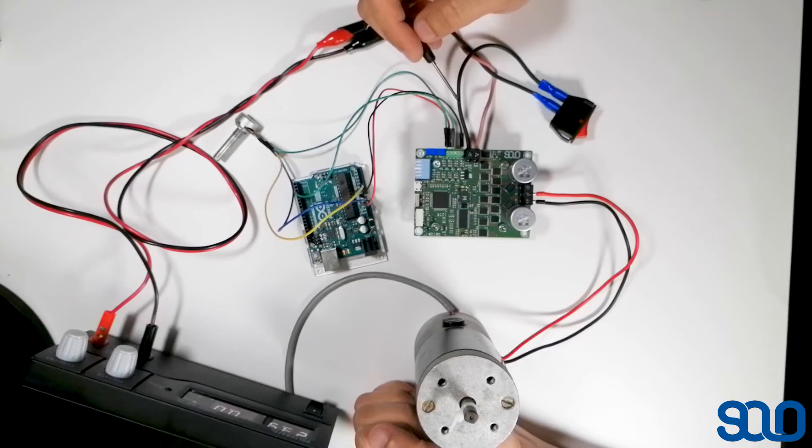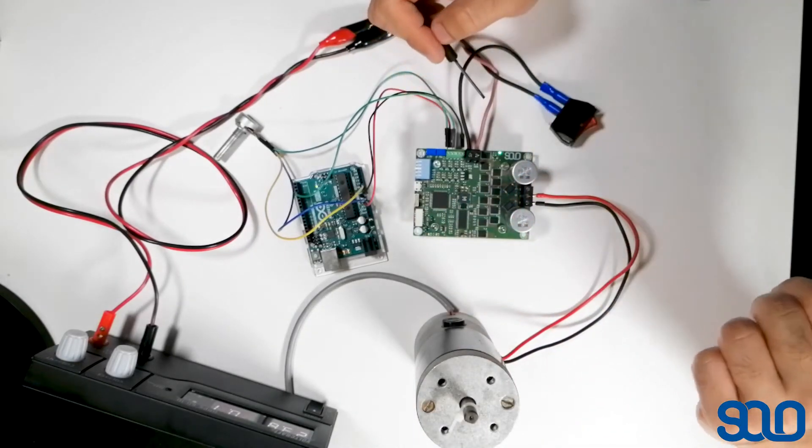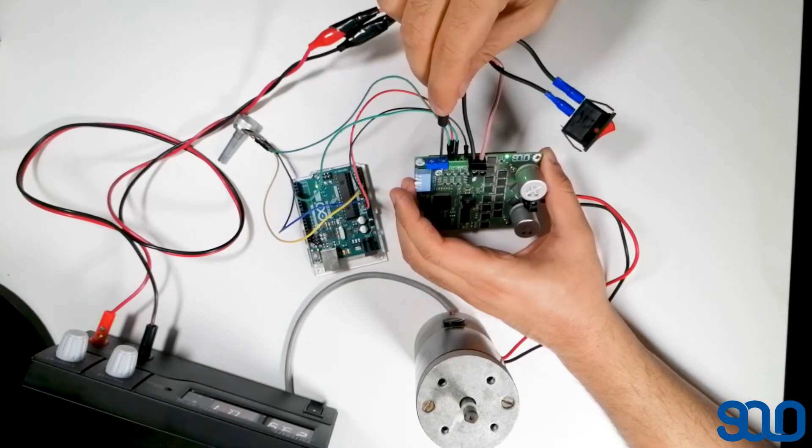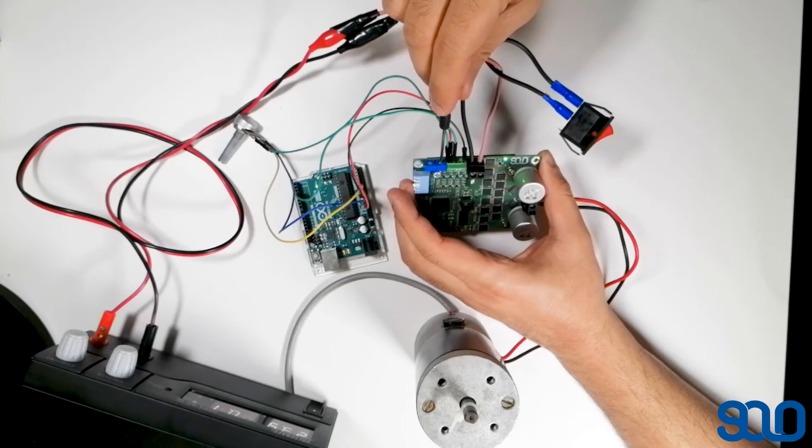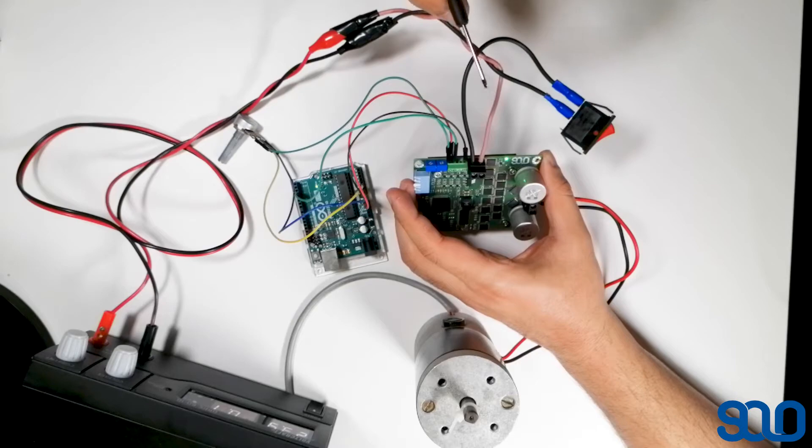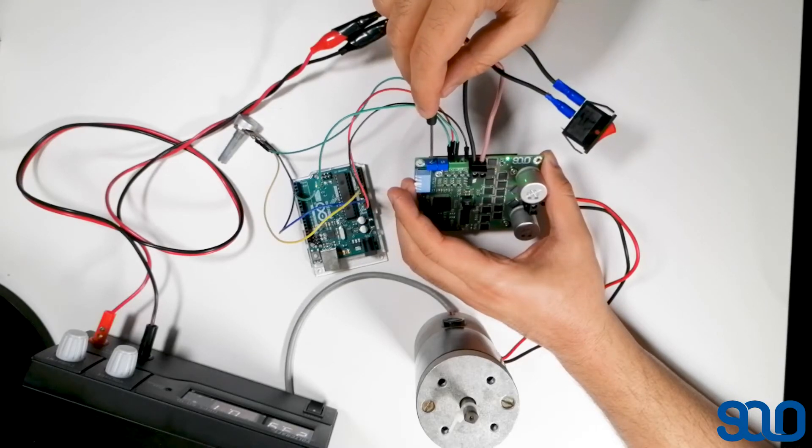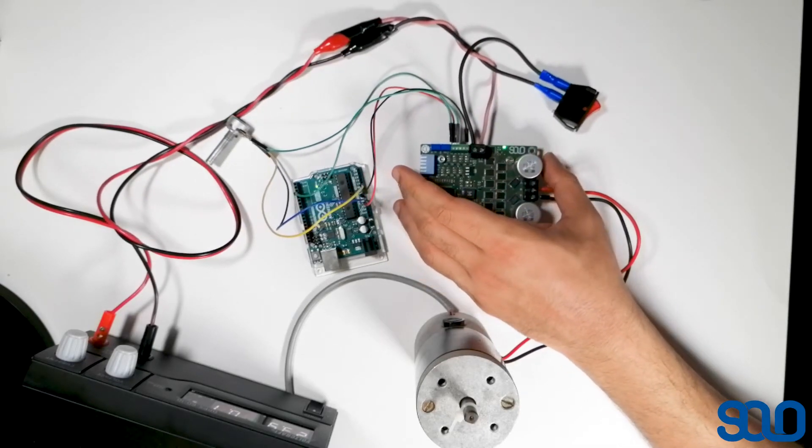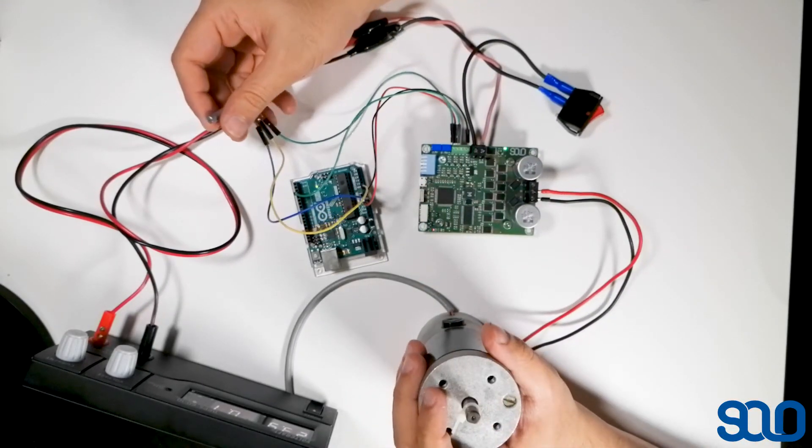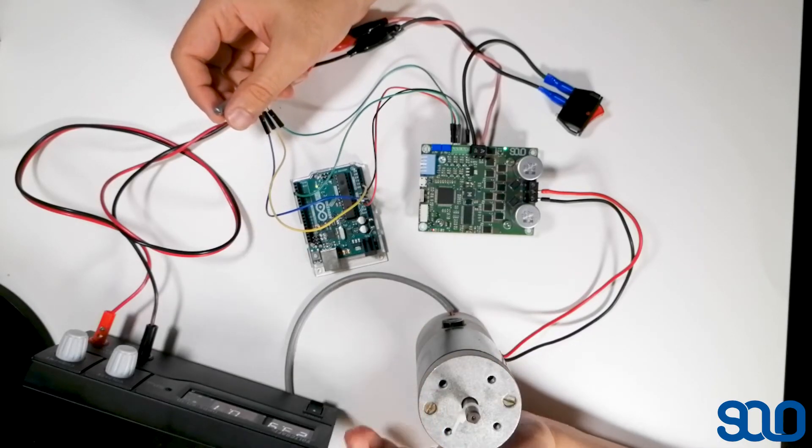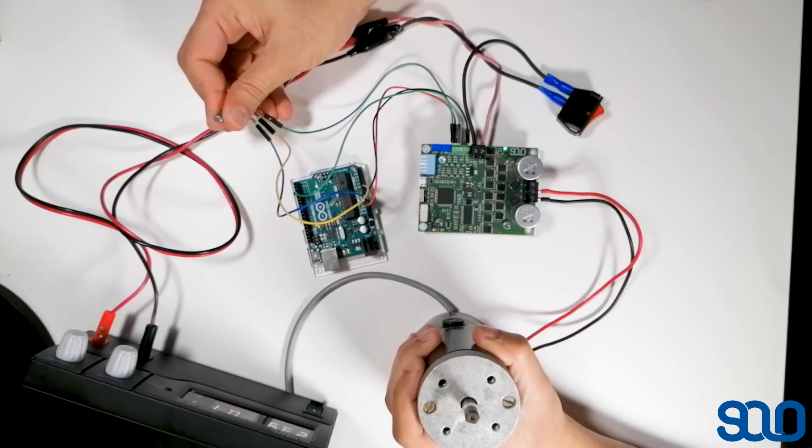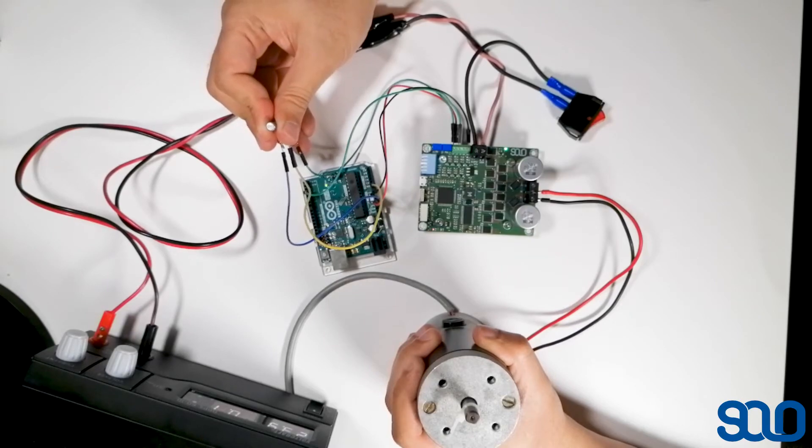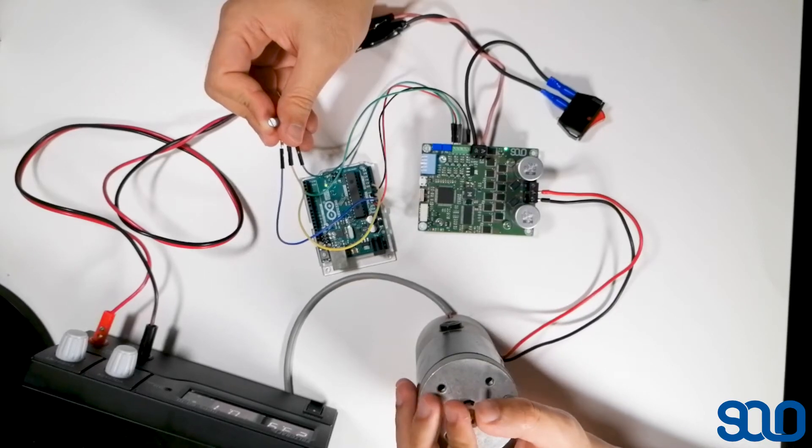In order to tune them, I turn on everything. The first thing you have to do is tune a little bit, just a little bit, the KP - maybe five degrees or something in the counterclockwise direction. I'm going to do that and add a little bit of KI, always much less than KP, maybe one degree. I'm going to see the behavior of the motor if it's okay or not. For most motors you just need to tune them a little bit and it remains the same forever as long as the motor is the same. I'm going to turn a little bit the potentiometer to see how it behaves. Seems to be controlling the speed. I'm going to put some load and see if it resists. Seems fine. I'm going to go to higher speeds.